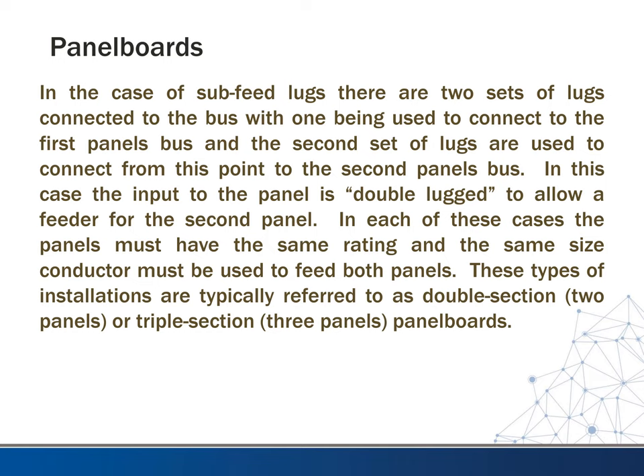So in each of these cases, the panels must have the same rating and the same size conductor must be used to feed both panels. These types of installations are typically referred to as double section, two panels, or triple section, three panel boards.